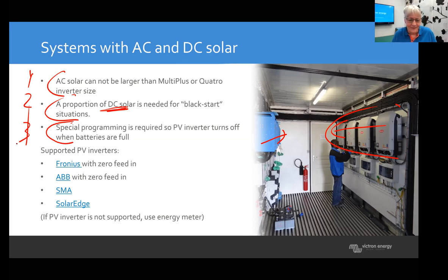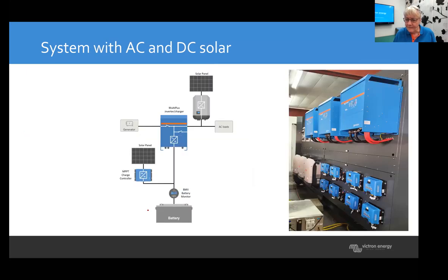Or use our new inverter chargers, or maybe already the new inverter unit. We support Fronius, ABB, SMA, SolarEdge. And if that's not supported, then you have to put an energy meter in the system, so the GX device can read out via the energy meter how much solar there is. But we don't use these communications for anything in an off-grid system, other than to show on our display how much PV is being generated. In an ESS system we do something with it, but in an off-grid system this is only for information purposes, not for control and not for doing anything else.